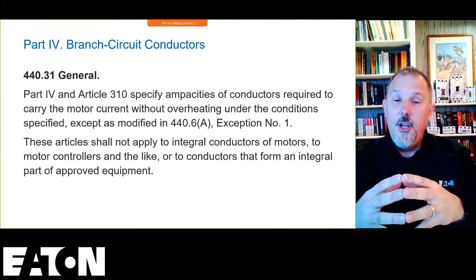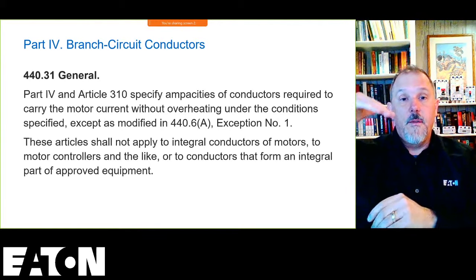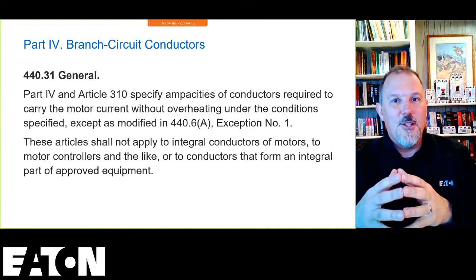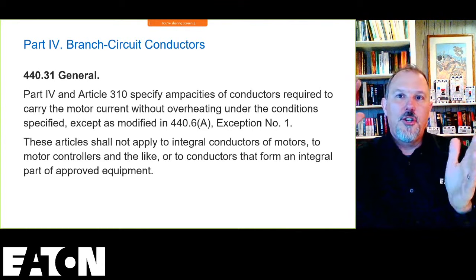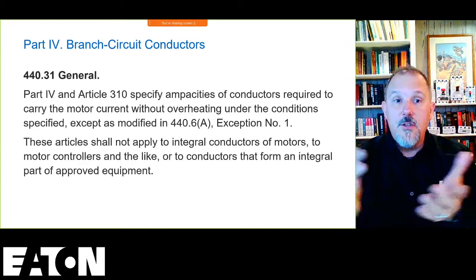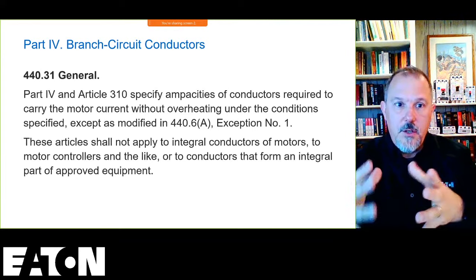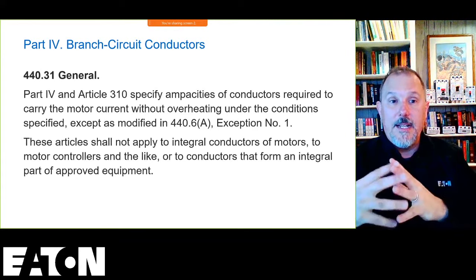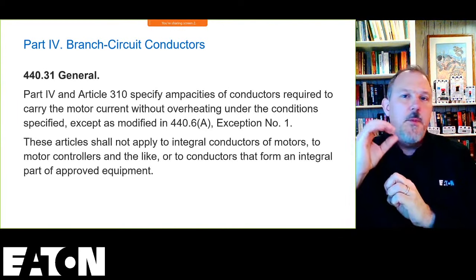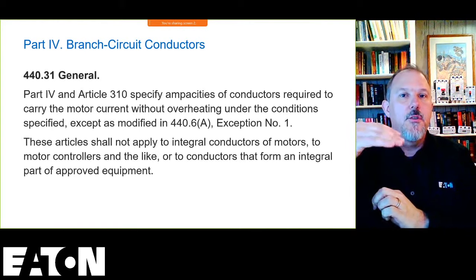You remember, when you have motors, you have two things to worry about. You have that equipment protection from a heating perspective, those are the long persistent overloads. And then you have to make sure that the motor starts from inrush. So your overcurrent protection and whatnot have to fit between those two. Your conductors are primarily concerned with the conditions of use to carry that motor current without overheating. And then your locked rotor amps, your starting currents, are going to be so short you're not really worried about that heating the conductor to failure. You're more worried about your persistent overloads.